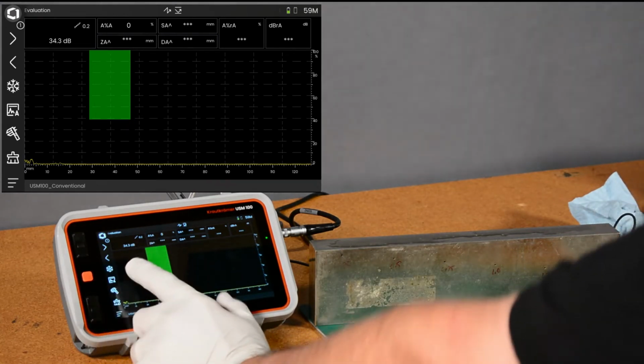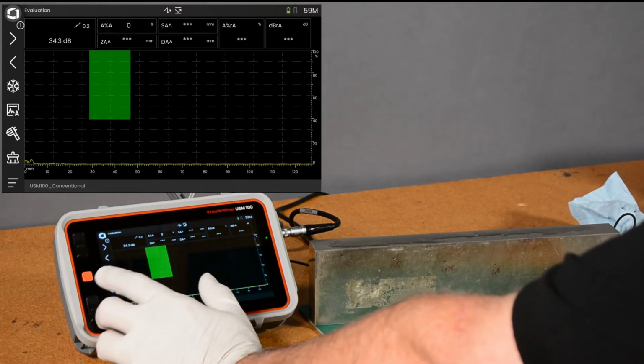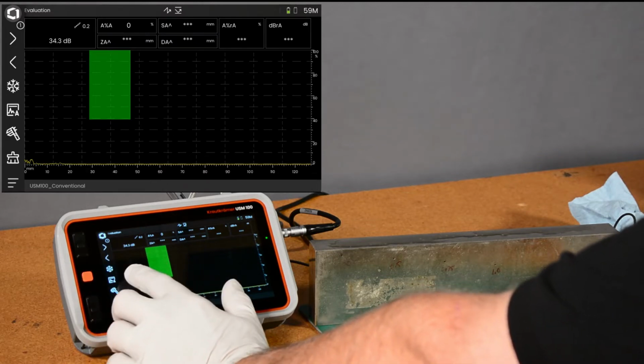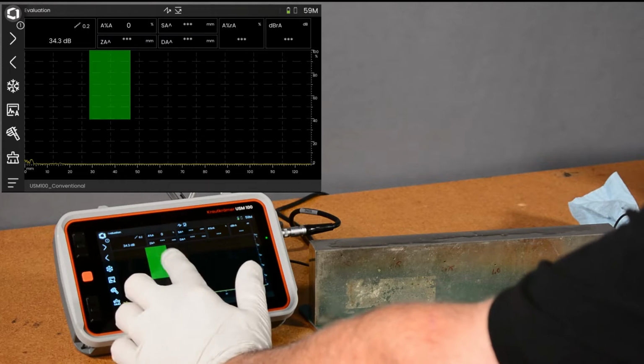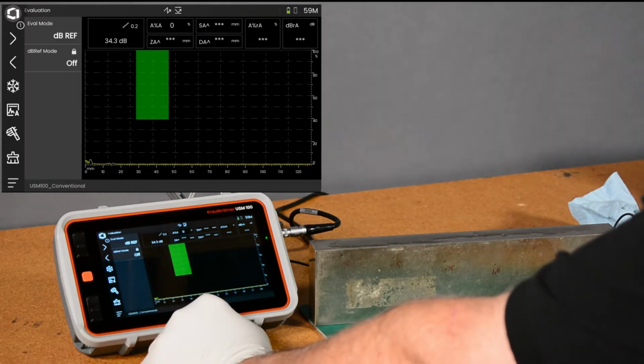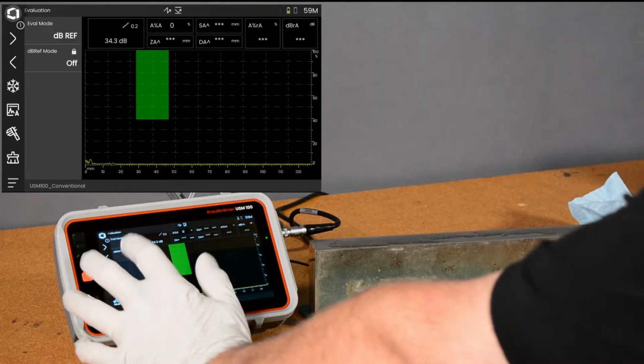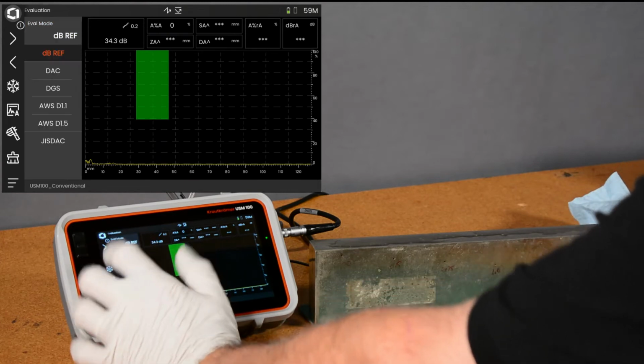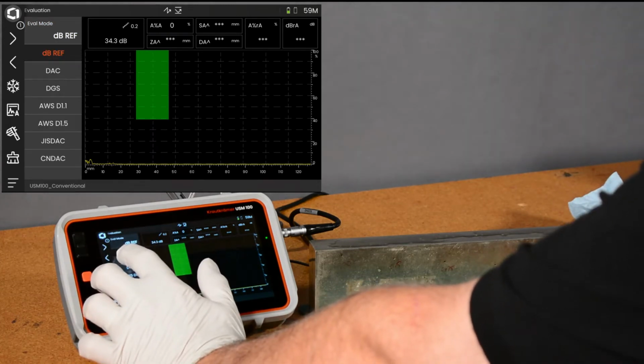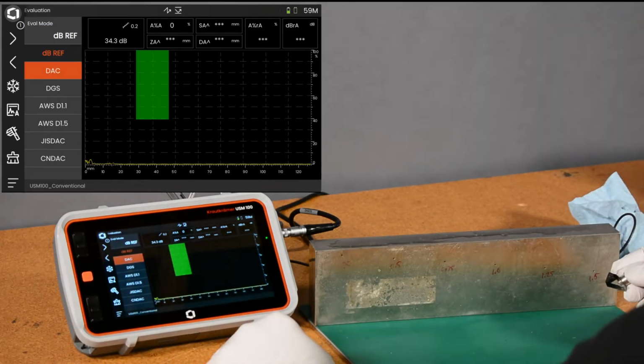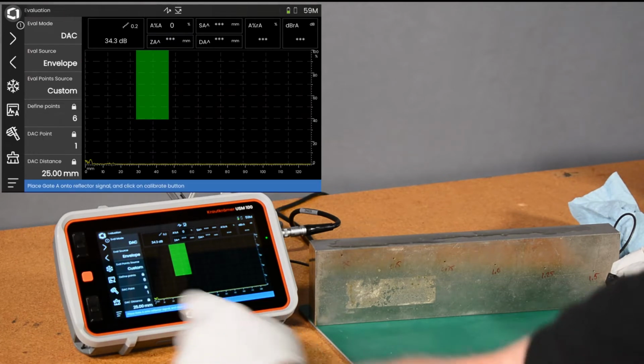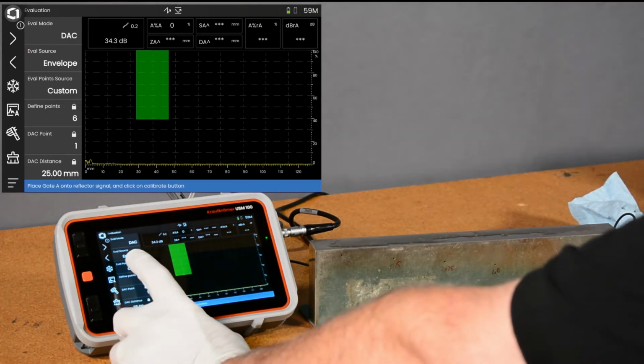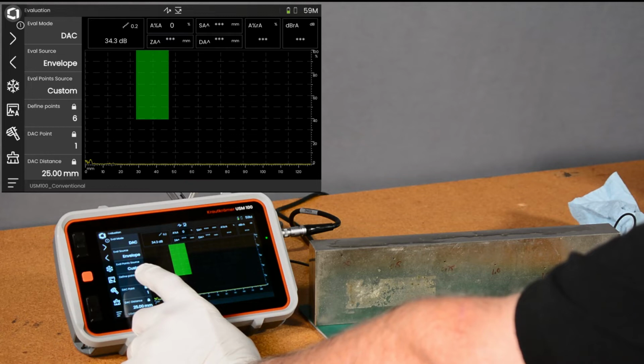So the first thing is we're on our evaluation panel since we've already done delay, velocity, and angle. If I swipe out the sidebar, the first thing I can do is choose my evaluation mode. By default it's dB REF. I'm going to select DAC instead, and that will change the menu, so now I have things that are appropriate for a DAC calibration.